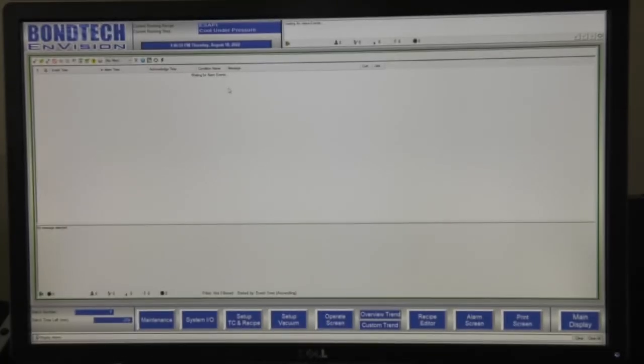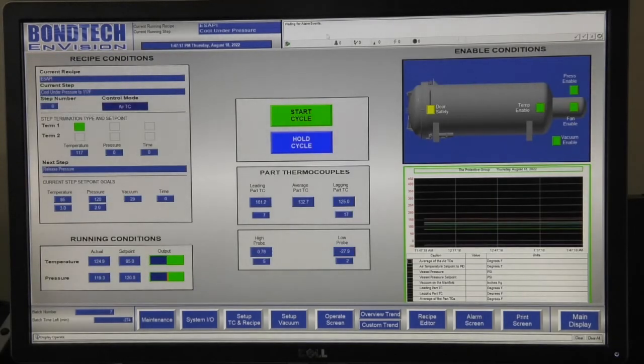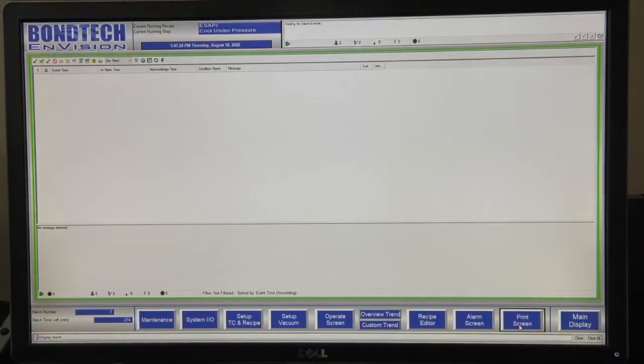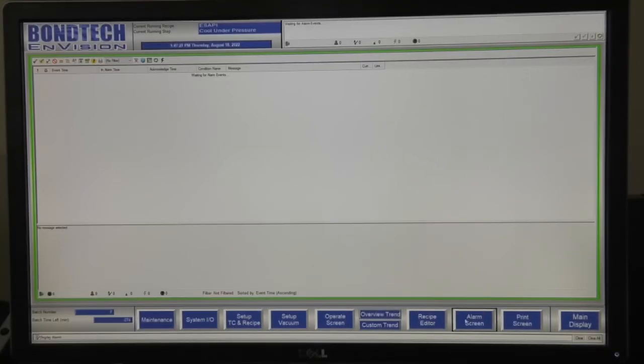The alarm screen shows if an individual alarm does go off, whether it has reached over temperature or over pressure, a door sensor has been triggered, whether something's been turned on or off, a vacuum transducer fails, or a thermocouple fails. This is where it would be shown, with a list of those alarms. And as you notice, on top of each individual screen there is an alarm indication up here in the top banner, so at any given time, no matter which screen you're on, it will show that particular alarm. And anytime you can print that screen, which is typically done on the trend screen, for reference for your records.